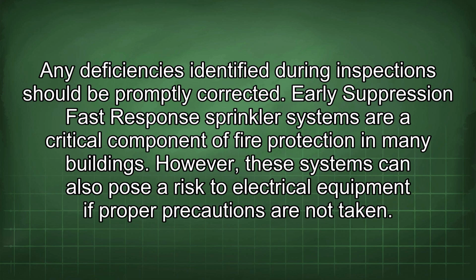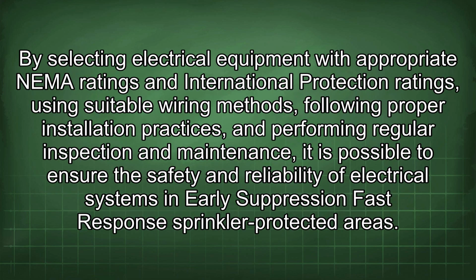Early suppression fast response sprinkler systems are a critical component of fire protection in many buildings. However, these systems can also pose a risk to electrical equipment if proper precautions are not taken. By selecting electrical equipment with appropriate NEMA ratings and international protection ratings, using suitable wiring methods, following proper installation practices, and performing regular inspection and maintenance, it is possible to ensure the safety and reliability of electrical systems in early suppression fast response sprinkler protected areas.